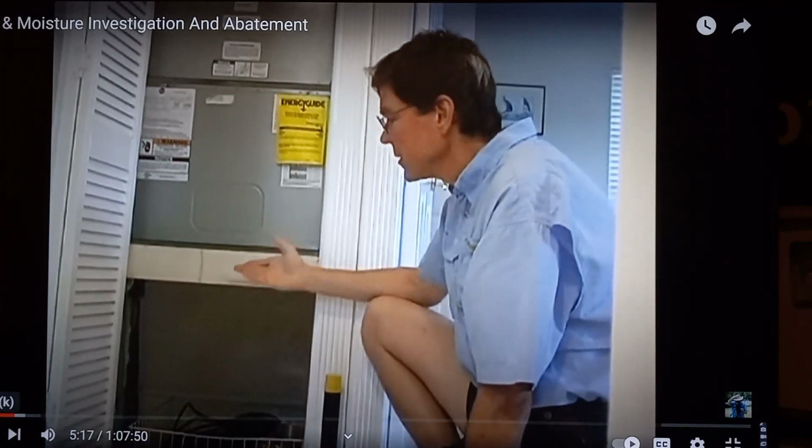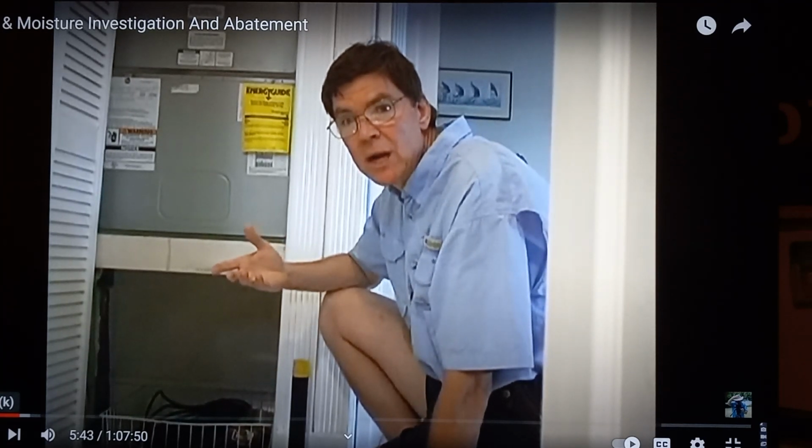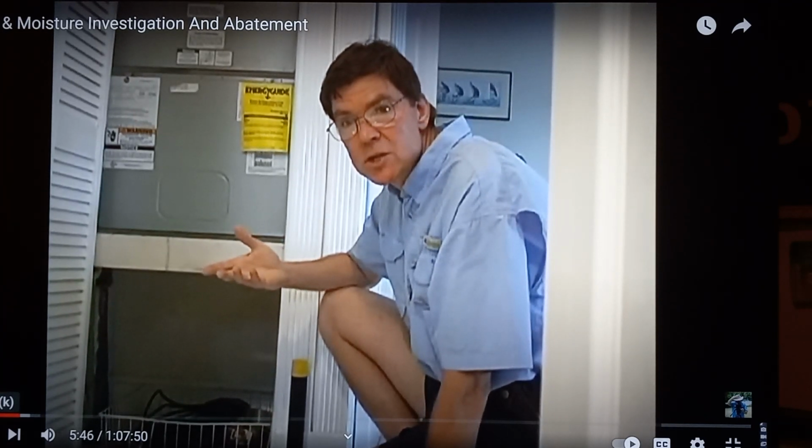Since the air handler is distributing air around the house, this is a good area to look for mold growth. We want to look at the air handler coils, the filter, the blower unit, and the adjacent walls around the unit. The air handler on cooling mode can have a lot of condensation around it, and therefore a lot of moisture. A unit that is not properly maintained and serviced can allow the condensate drain to clog up, and this will back up around the unit and create favorable conditions for mold growth.